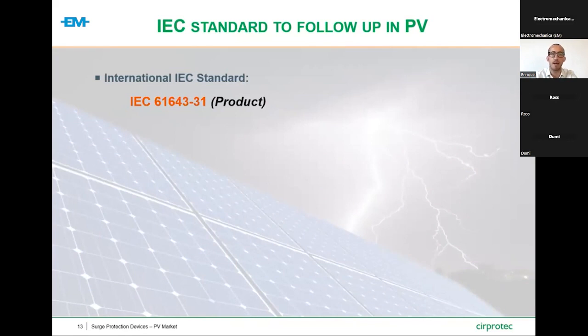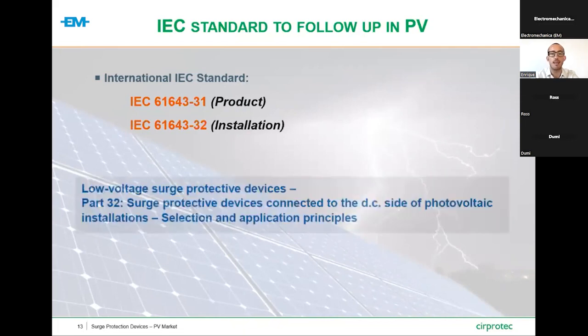It's defining the parameters all the SPD manufacturers should follow up to be sure we are manufacturing the products according with the standards. And then the IEC launched as well a specific standard finished by -32 that is focused in the installation principles to guide every installer focusing PV to be sure they are installing and protecting each PV installation according with the standards statements.